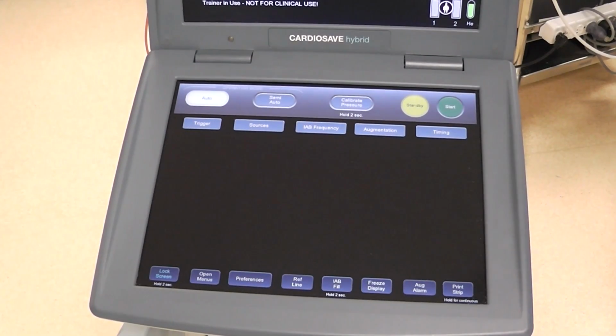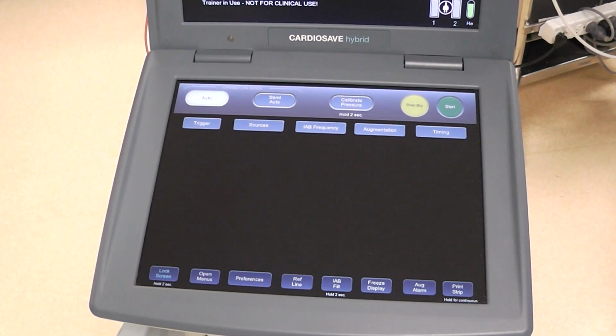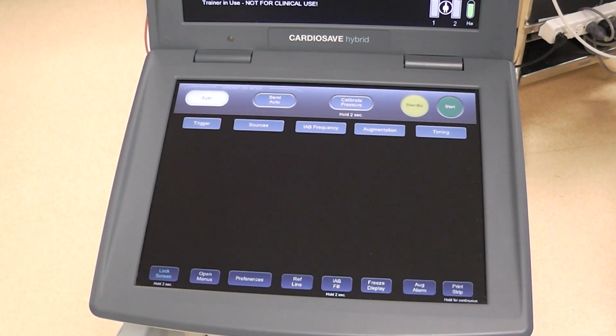This is the lower screen of the console, and as you can see, when you turn it on, it is set into auto mode, which means that the machine will decide when to inflate and deflate the balloon. It's also set to standby. Now, if you are using the fiber optic sensor that's part of the balloon, you can just start using the machine right away as is.